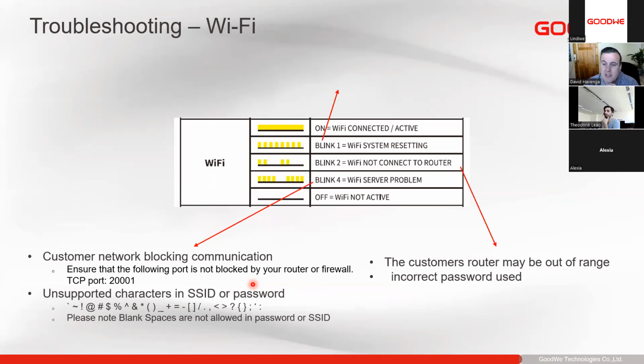Sometimes it might block the communication after 1 week, sometimes it might block the communication after 1 month. Especially if you see the customer does a reset, it works again, 1 week or 1 month later it disconnects again, and then goes back to 4 flashes. That is a clear sign that there is an issue with the firewall blocking the communication. The only way then is to port forward on the router to make sure that the port is permanently open for the inverter to communicate on.